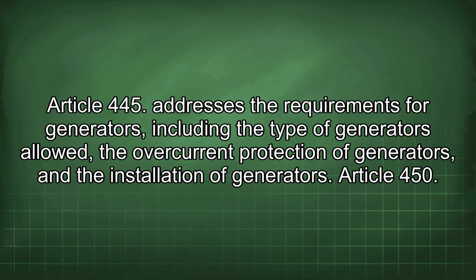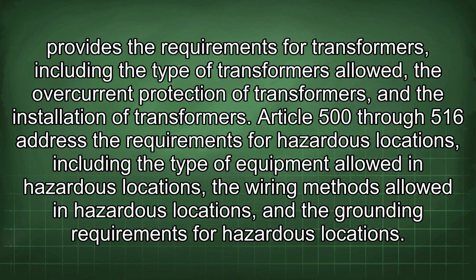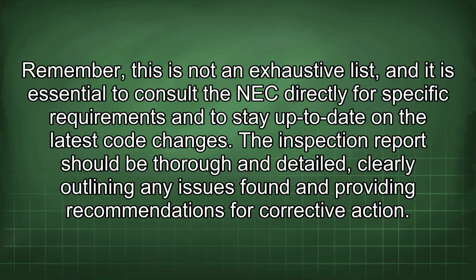Article 445 addresses the requirements for generators, including the type of generators allowed, the overcurrent protection of generators, and the installation of generators. Article 450 provides the requirements for transformers, including the type of transformers allowed, the overcurrent protection of transformers, and the installation of transformers. Articles 500 through 516 address the requirements for hazardous locations, including the type of equipment allowed in hazardous locations, the wiring methods allowed in hazardous locations, and the grounding requirements for hazardous locations. Remember, this is not an exhaustive list, and it is essential to consult the NEC directly for specific requirements and to stay up to date on the latest code changes.